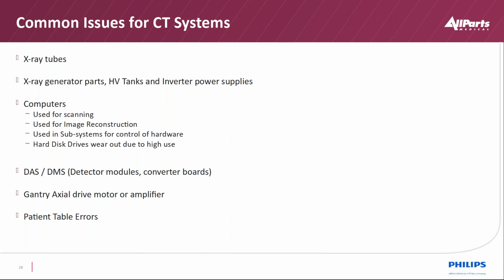And then we also have the X-ray generator supporting parts, such as inverters, high voltage tanks, and the controls for those, which are high usage as well because we're using a lot of current through the X-ray tube. With regards to computers, we're not only controlling the system, calling out protocols, and using the user interface to initiate a scan, but with that raw volumetric data set we're pulling data out of it, depending on which frequency response filter we want to enhance bone or soft tissue. We can also cross-plane instead of just producing images from an axial perspective. We could also do it periaxial, like along the length of the optic nerve. So we could take that data set, and once it is used to produce a complete DICOM image set, that would be overwritten.